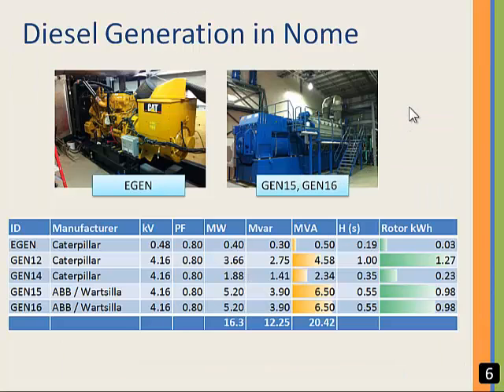Here is the generator lineup at Nome. Yellow bars highlight volt ampere ratings. Green bars highlight rotor kinetic energy. Kinetic energy is highly desirable to sustain frequency under disturbances. However, as seen, these machines do not store very much of it. Therefore, we can consider supplementing this energy storage with an external unit to support frequency regulation.